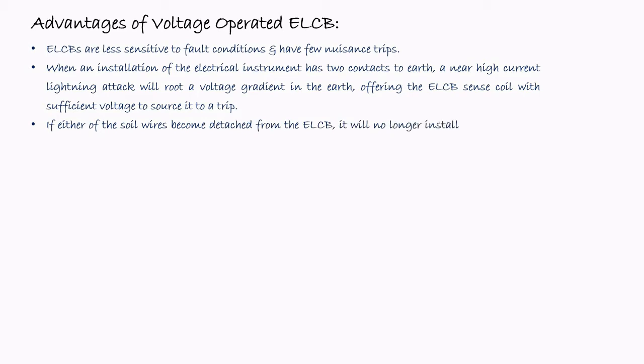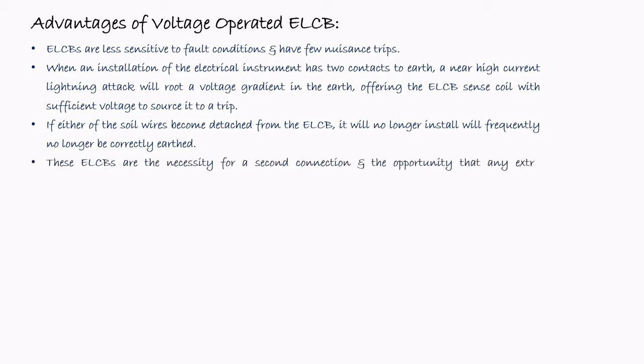If either of the earth wires becomes detached from the ELCB, the installation will frequently no longer be correctly earthed. This ELCB needs a second connection, and any extra connection to the ground on the protected system can inactivate the detector.